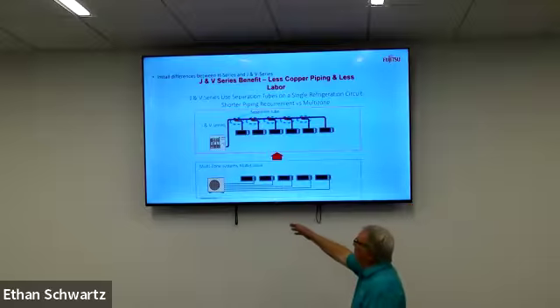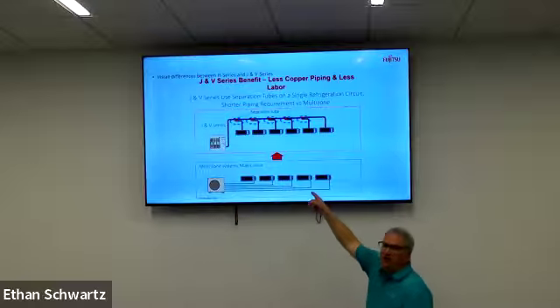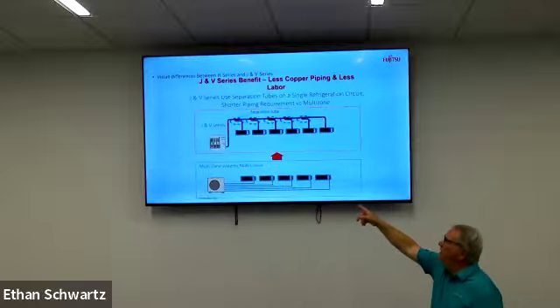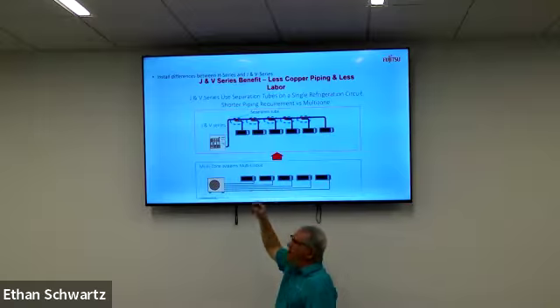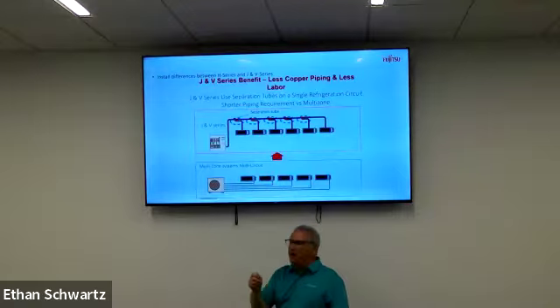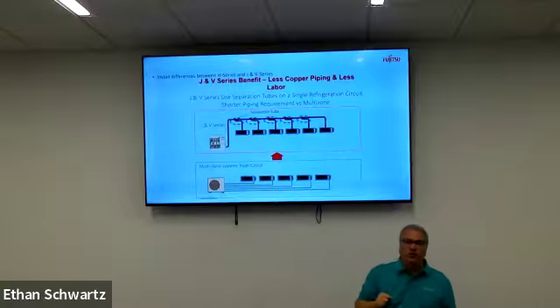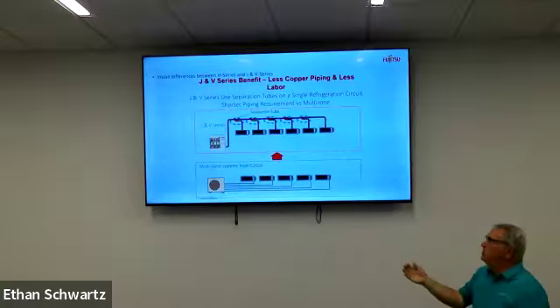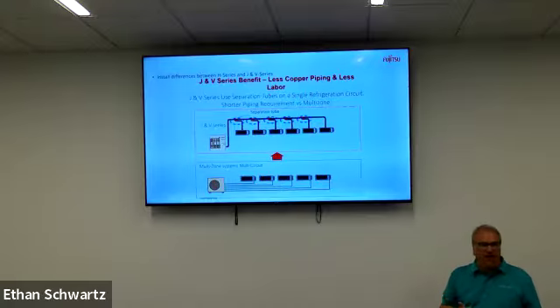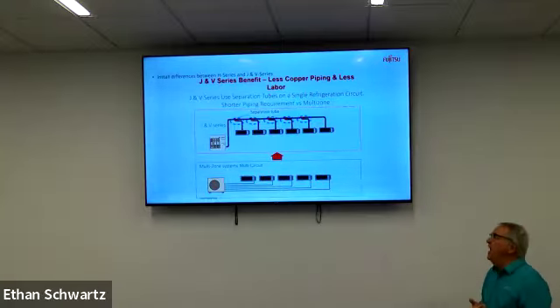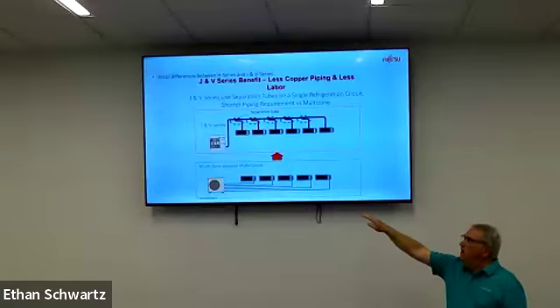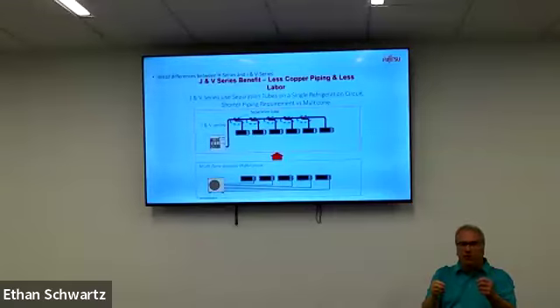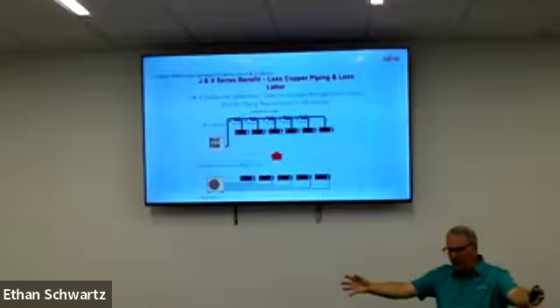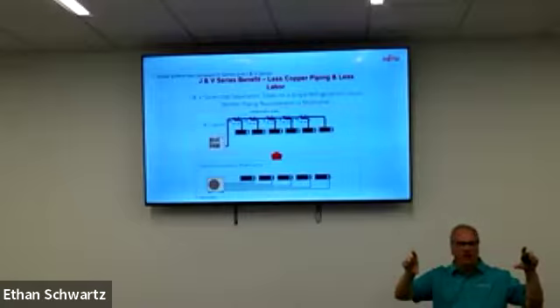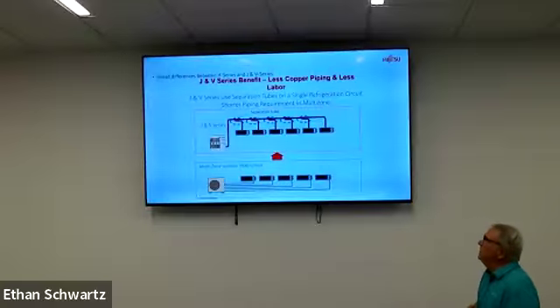So, and maybe this is a 3-ton. So if we think about the J series, where we have a 3-ton, it is a heat pump product. It has a liquid line, a suction line, but now we have separation tubes that allow us to branch off within the space. Or we have a header kit that allows us to come from the outdoor unit to one spot within the structure and then branch off. It's kind of like a hydronic manifold, and then send the pipes out to the indoor units. That's number one.